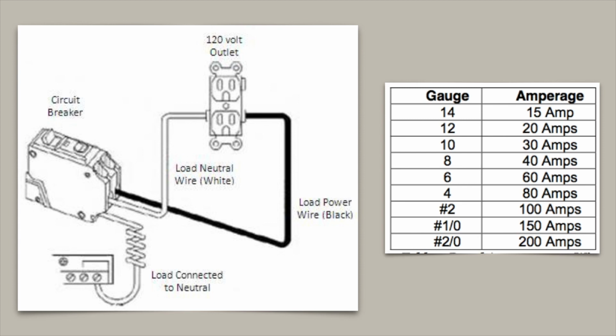The home inspector, when performing an electrical inspection of the main panel, must take off the cover and match the proper size breakers with the wire that is handling the current. A 14 gauge wire protected by a 20 amp breaker is a safety defect because the wire could overheat before the breaker is tripped. The circuit could have extended periods of 18 amps on it. The 20 amp breaker won't trip while the 14 gauge wire is overheating. This will start a fire in the walls and may lead to property damage, injury, or death. This is one of the most important things we inspect.